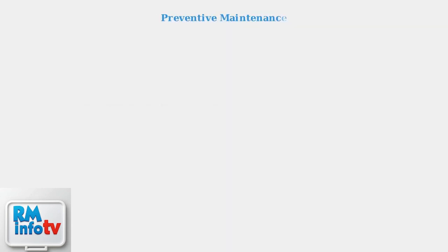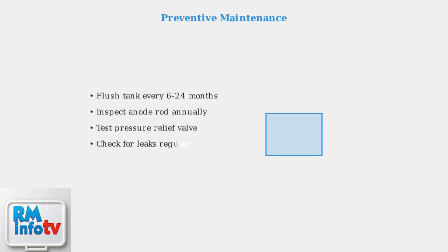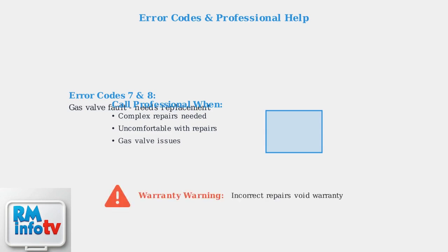Regular maintenance can prevent many of these issues. Flush the tank every 6 to 24 months, depending on your water hardness, and inspect the anode rod for corrosion. Modern Bradford White water heaters display error codes to help diagnose problems. Error codes 7 and 8 indicate a gas valve fault requiring replacement. Remember that incorrect installation or inadequate maintenance can void your warranty. When in doubt, consult a qualified technician to ensure proper repairs and maintain warranty coverage.